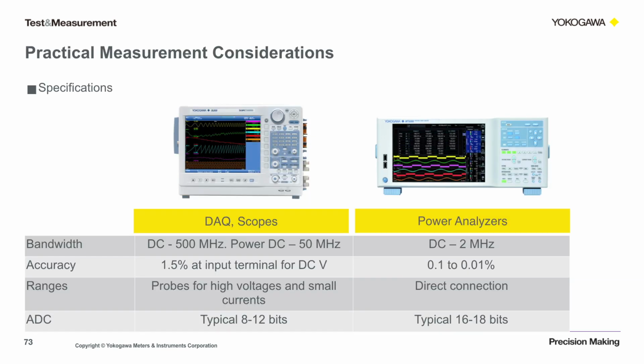The main difference between these instruments is bandwidth. Generally, power measurements are properly digitized with 1 to 2 megahertz. But if some other signals on your test are of higher voltage or higher bandwidth, a power analyzer might not be adequate. You generally want to choose an instrument that has 3 times the frequency of the fundamental. A power analyzer is going to have a higher resolution ADC as well. This is the nature of ADCs on the market, since there really aren't any 18-bit ADCs at 500 megahertz and up. The last is accuracy. The scope is rated to generally 1.5%, where the power analyzer can go down to 0.01%.